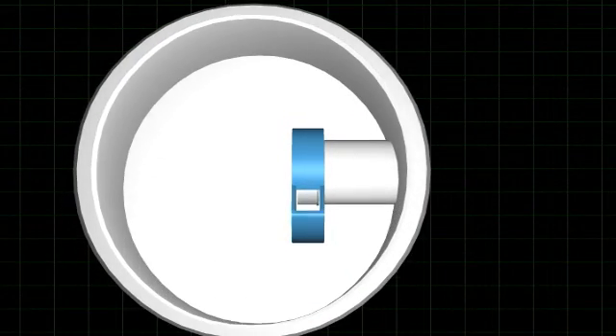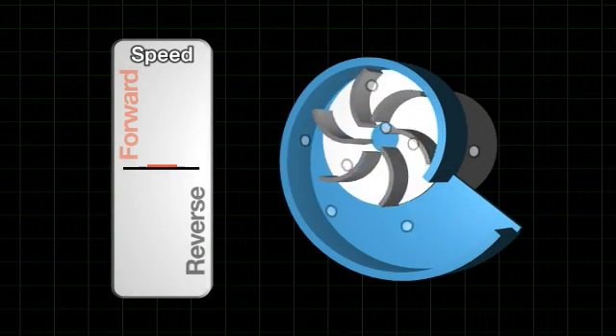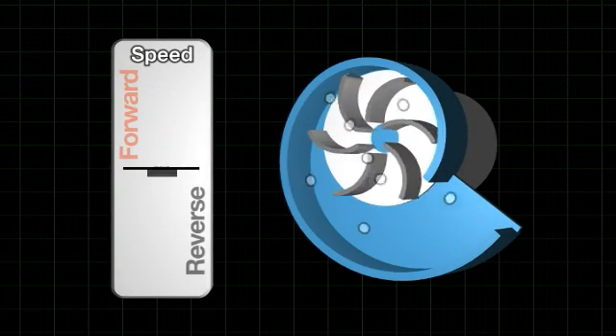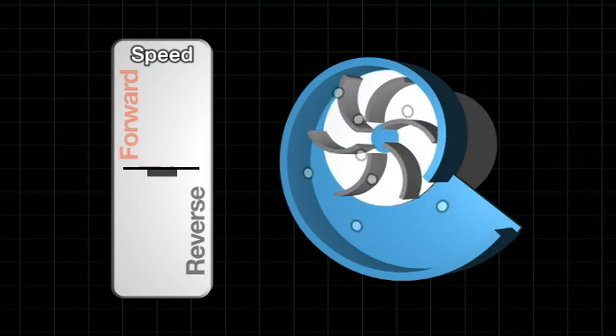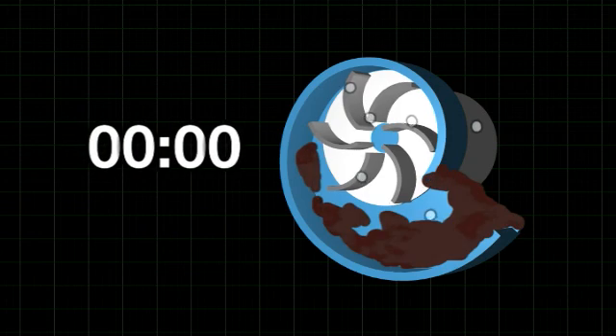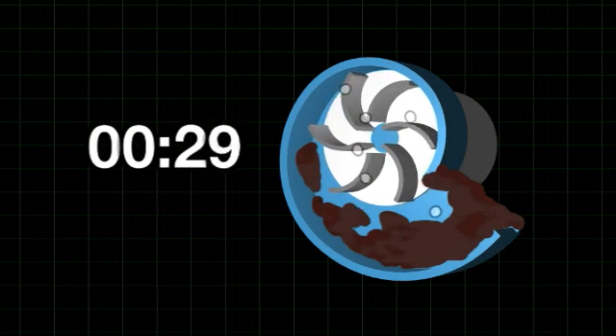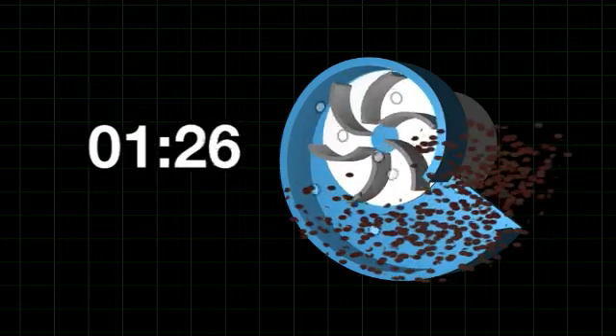The anti-jam software is a clever program that performs a number of cleaning cycles every time the pump starts. Each cycle consists of a series of rapid ramp-ups in both forward and reverse directions until the fouling is removed, but without stressing the motor. Taking one to two minutes to complete, the cleaning cycle removes the debris from around the pump, preventing it from entering the pump and blocking it when the pump ramps up from zero to its normal operating speed.